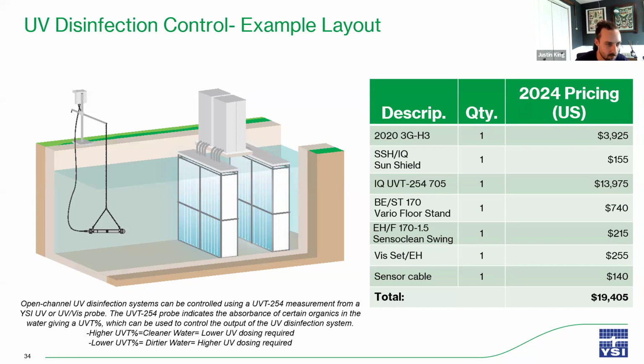And a system like this, just a UVT probe as well as a controller, ends up being around $20,000, and the return on investment is typically short, like we see with the orthophosphate analyzers, within a year, because of the amount of energy we end up saving on UV lamps. And you can also include the lamp bulb replacements. If we're running the UV lamps at a highly efficient rate, the amount of time in which you need to change them out will increase. So there's a lot of added cost savings to implementing an online system with the UVT system.